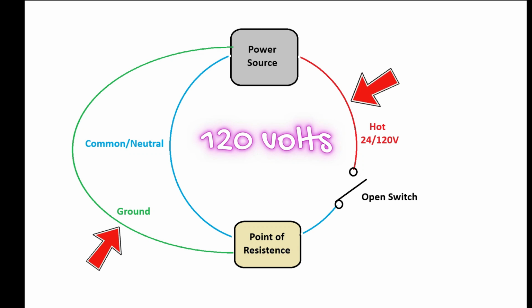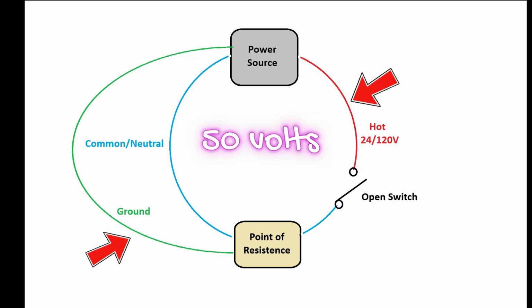But you always want to default to common or a neutral wire to get an actual voltage reading, and then just verify by using your ground to see if you're getting the same thing. So if I went from hot to common or neutral, I read 120, and then I went from hot to ground and I read 120, that's telling me I have a properly grounded system. If I have 120 between hot and neutral, but like 50 or 60 volts between hot and ground, that's telling me I don't have a properly grounded circuit.